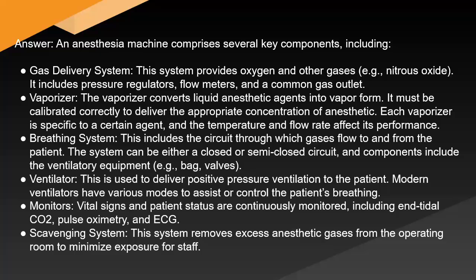Vaporizer. The vaporizer converts liquid anesthetic agents into vapor form. It must be calibrated correctly to deliver the appropriate concentration of anesthetic. Each vaporizer is specific to a certain agent, and the temperature and flow rate affect its performance. Breathing system. This includes the circuit through which gases flow to and from the patient. The system can be either a closed or semi-closed circuit, and components include the ventilatory equipment, e.g.